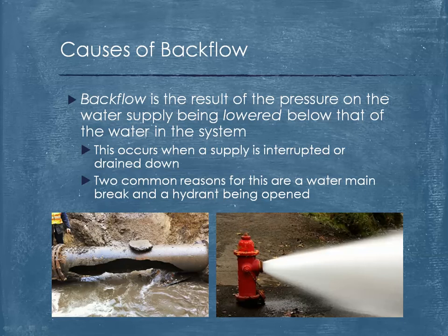First, I want you to think about a large main water pipe running under the street outside the restaurant. If that pipe should break due to the age of the pipe, or even a construction crew digging in the area, a large volume of water will quickly flow out of that water main pipe. The volume of water escaping that water main is significantly more than the amount of water in the small pipes located inside the restaurant. All the water escaping the main pipe causes such a pressure change that it can actually pull water from all the surrounding pipes, such as those inside the restaurant.